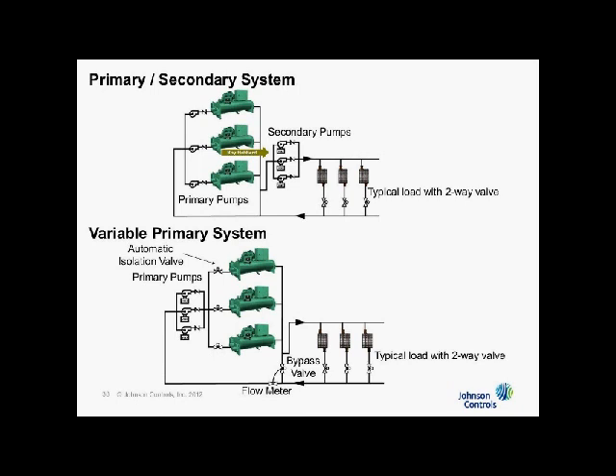But I do have still some sort of bypass down here. With my primary-secondary, we have a larger bypass that's design criteria is typically the same size as the headers. It's usually 8 to 10 pipe diameters long in order to prevent transient temperature exchange, and it's usually designed to be as close to zero pressure drop as possible. This, however, is much, much smaller. The pipe is sized to be roughly the same as the minimum flow of the largest chiller you have, or operating chillers. So it's much smaller, and we do need a pressure drop, which we'll explain a little more about later.